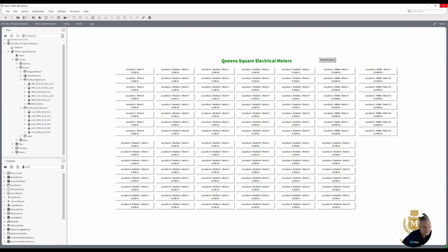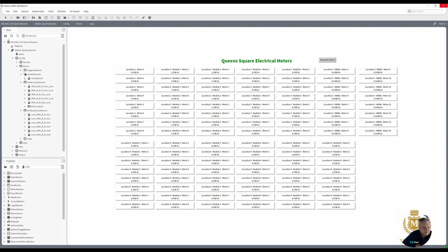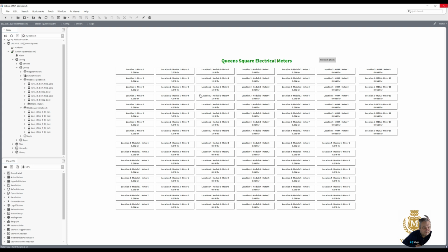So there's your Modbus TCP network. That's your ISMA network, but as you know, we've only got four digital inputs, so we can only use four of them as a counter. I haven't actually included that in this main sheet because I think they're going to go to a JACE 8000 and not use a MAC 36 anymore. They were going to use a MAC 36 because it had 16 universal inputs, but they cannot be pulse counters. It can only be digital inputs.